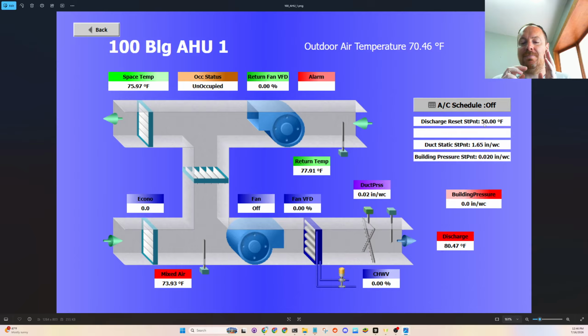That is where we could do Guideline 36. They do have some really neat things, like being able to reset air handling unit temperature and pressure based off of demand. So you're looking at VAV box airflows, air damper positions, zone temperature and set point deviations, and then we can implement an algorithm on the air handling unit, and it works pretty good. So that's the strategies.